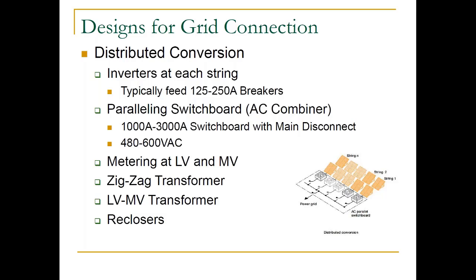And it's typically nowadays group-mounted thermal mag circuit breakers at the AC paralleling level. So if you can see the little highlight where they all parallel together, there's going to be usually group-mounted AC circuit breakers. In between there, where the group-mounted circuit breakers are, and the power grid connection, there's going to be some type of customer metering. There may be a utility metering or monitoring system there as well. And then there's going to be the main disconnect out to the grid. And I'll go through a little bit of the different designs that we've seen and implemented here, as well as some of the options that States can certainly integrate for a customer or utility, depending on the installation requirements.